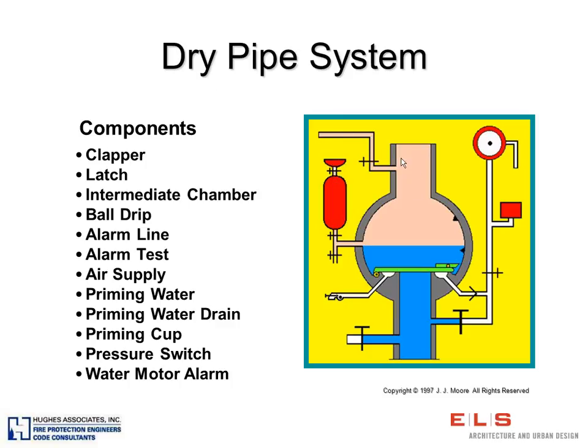In a dry pipe type system, I want you to keep in mind that each sprinkler is what we call closed. So that means if you have a fire, it's highly likely only one sprinkler, or maybe 2 or 3 sprinklers, is going to control that fire. And so each sprinkler has its own individual heat element, and so when it opens up, only those sprinklers that have fused or opened will allow water to come through. And so that's typical for a dry pipe system, that we have what we call closed sprinklers.